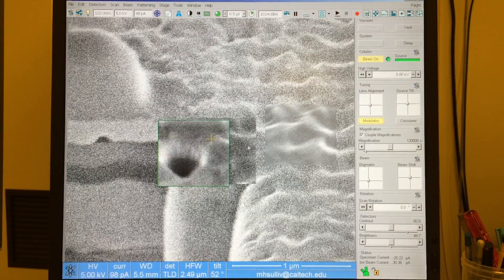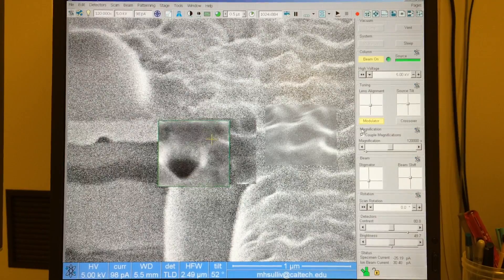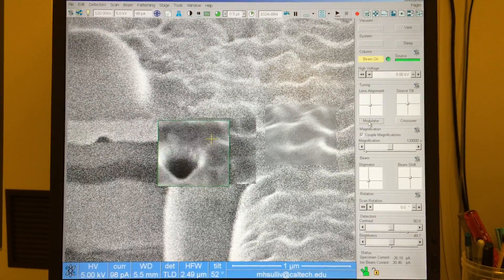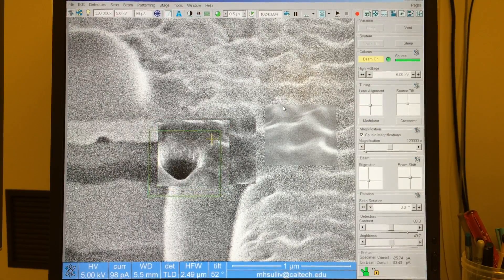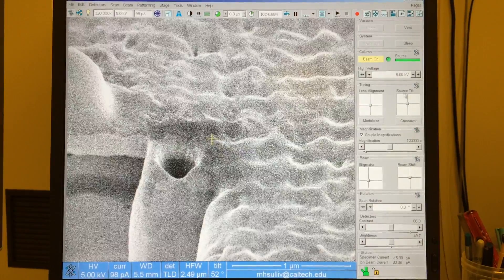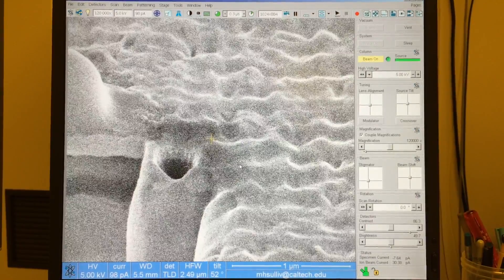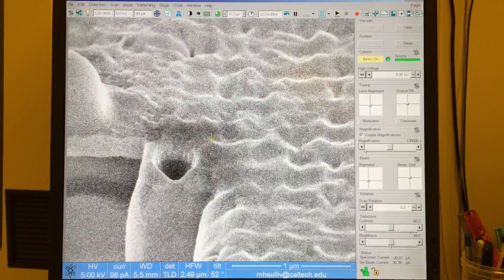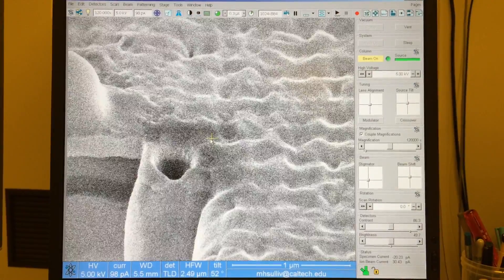And here, basically, it's just blinking in place, which is what we're looking for. So I'll turn off the modulator. And I want to note here that I did not go in and adjust the source tilt. I had done that in field-free mode. When you jump from field-free to immersion mode, it does not affect the crossover.